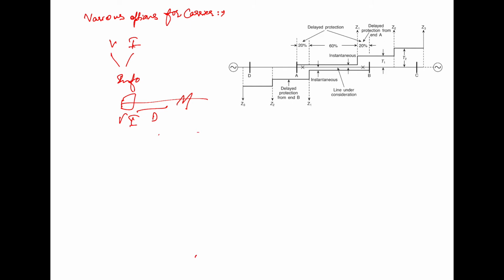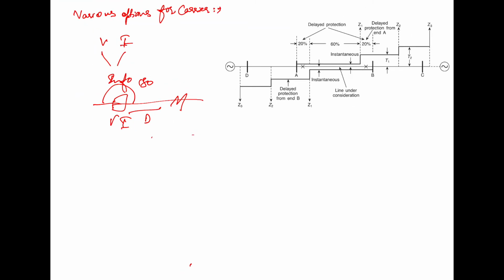However, there is no ambiguity about the fault from the end near to the fault, because as the fault moves from just beyond the bus to just ahead of it, there is a 180 degree change in phase of the current at the nearest end. Thus the nearest end has clear-cut information, which is so difficult to extract using the power frequency current and voltage at the remote end.